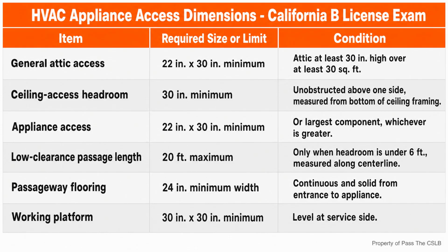I put the key dimensions into one reference table. Read it as a journey. 22 by 30 is the baseline opening. 30 inches of headroom matters above a ceiling access. 24 inches is the solid path. 30 by 30 is the work area at the service side. 20 feet is the special travel limit when the passageway headroom is less than 6 feet. The largest component rule can override the baseline opening size.